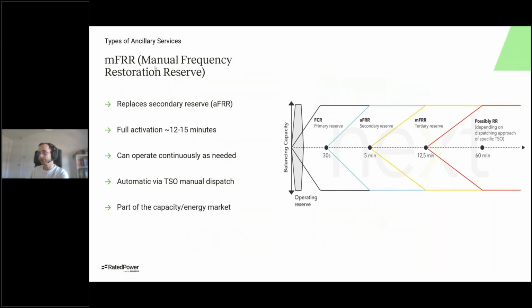Then we have manual frequency restoration reserve. So this is the tertiary one. The objective is to replace the secondary reserves. If there's no more secondary reserves, then this will come into place. It takes a bit longer to activate, between 12 to 15 minutes. Again, it can operate continuously as needed. This is also triggered manually by the TSO, so typically through the SCADA systems or just a phone call before. And also depending on the market, it can be part of the capacity or the energy market.